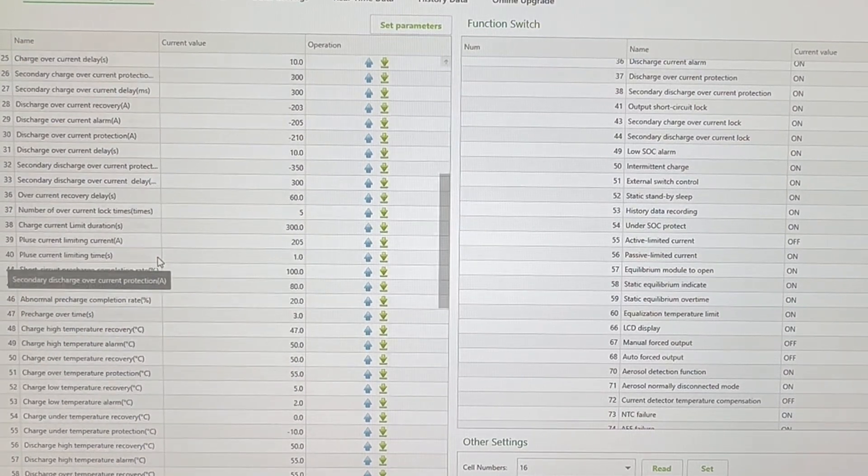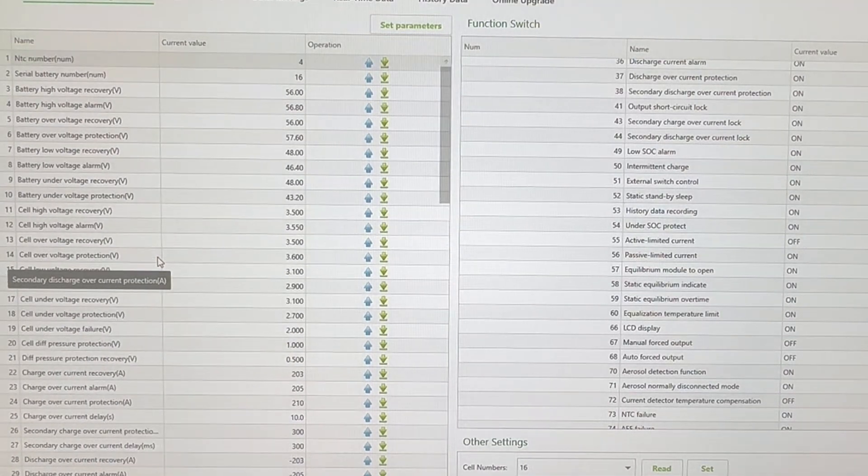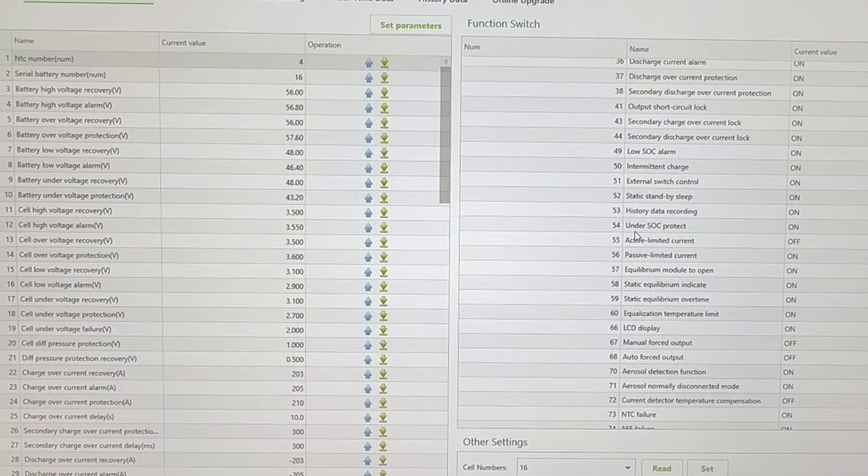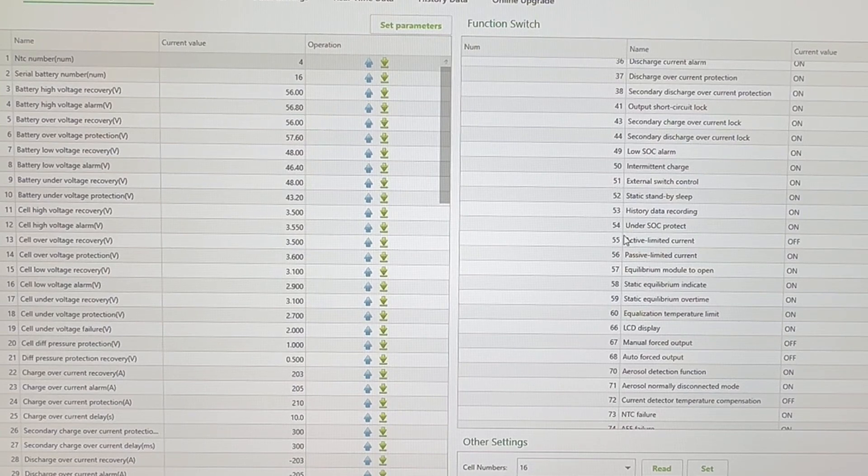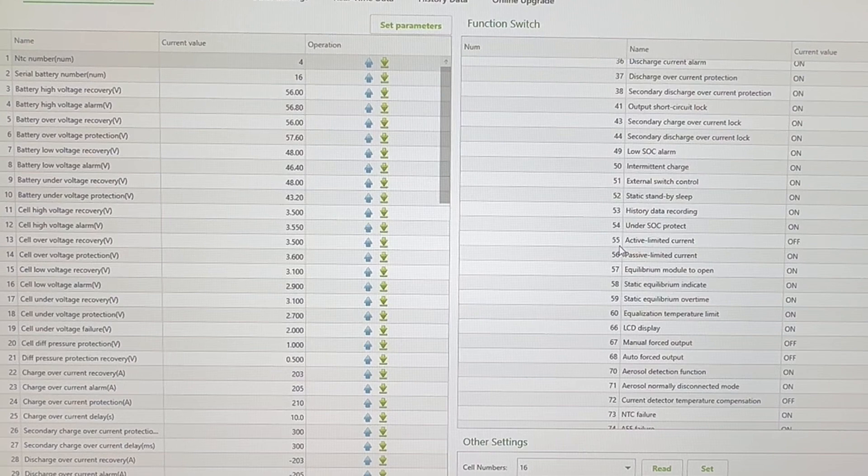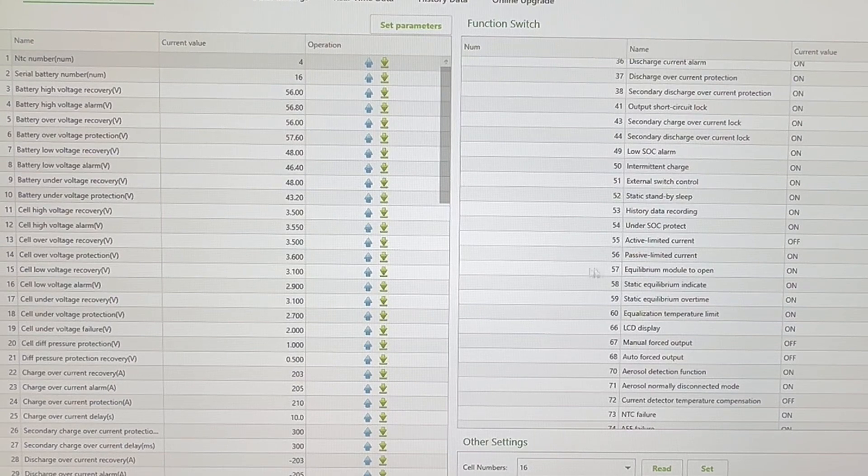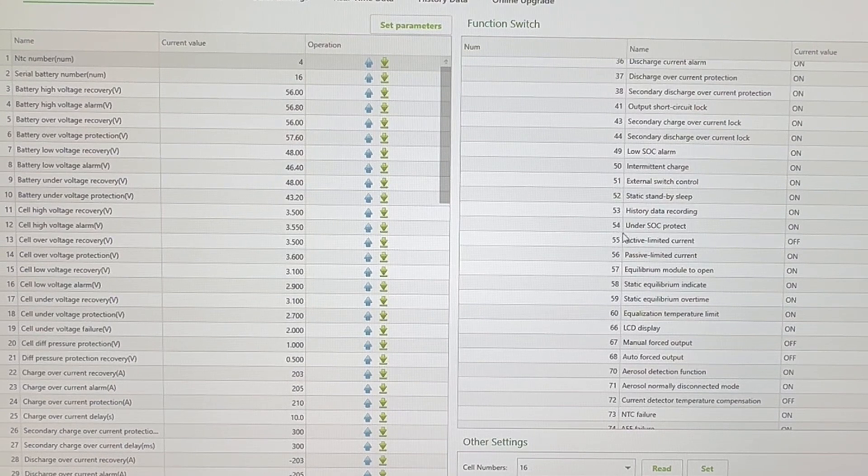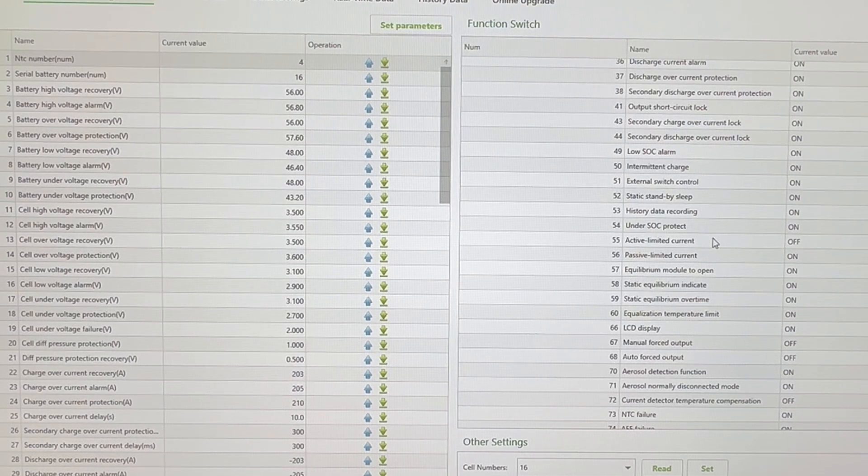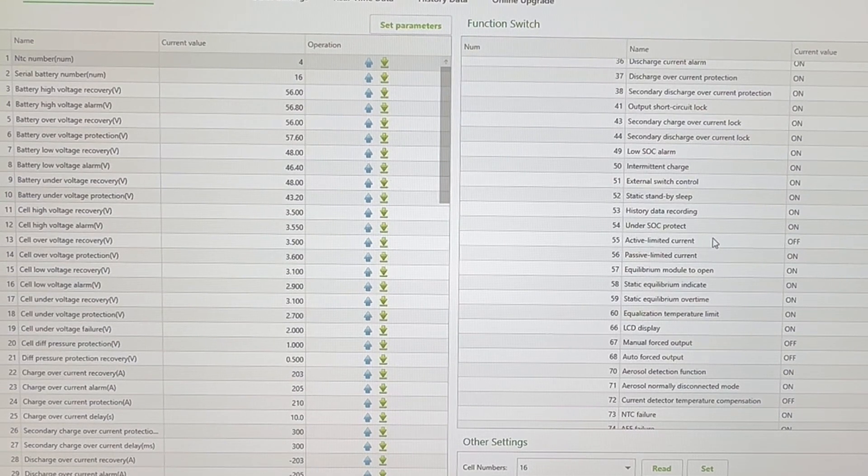And I believe that what happens is the setting will be over here as well, and whatever parameter you have that set on, whatever voltage you have that set on, it basically just activates here. So if your battery pack falls below a certain voltage, it will turn the battery pack off to protect it from degradation. So I would suggest turning line 54 in this case, under state of charge protect, turn that on. So I've now done that on all three battery packs.